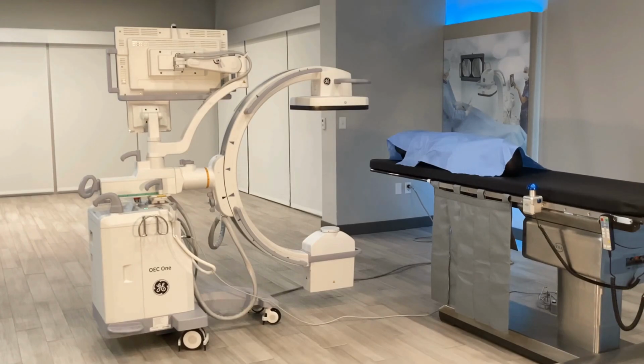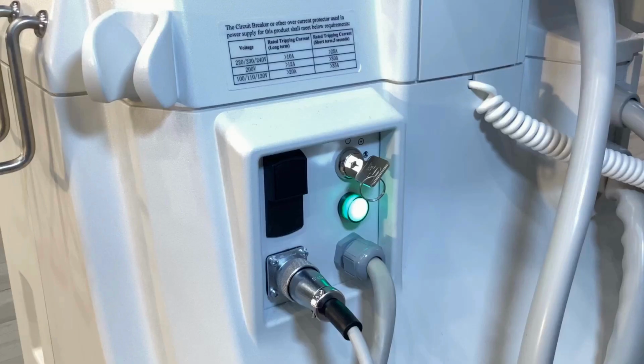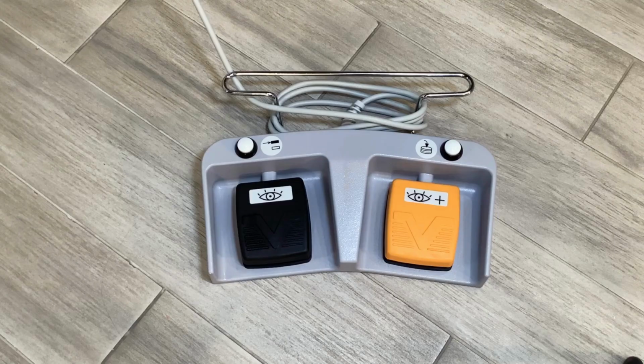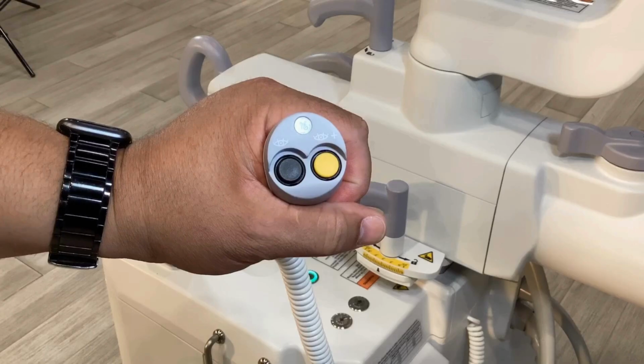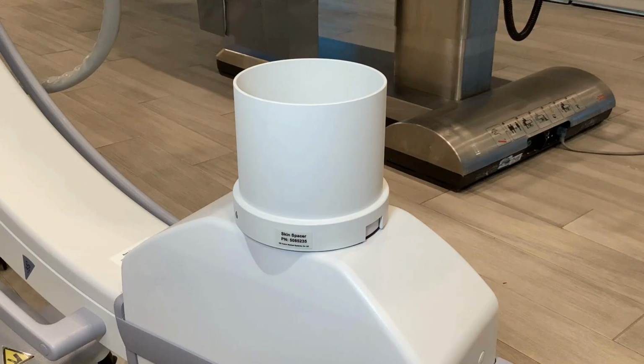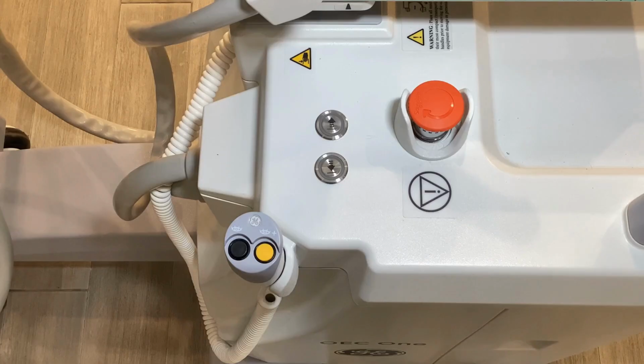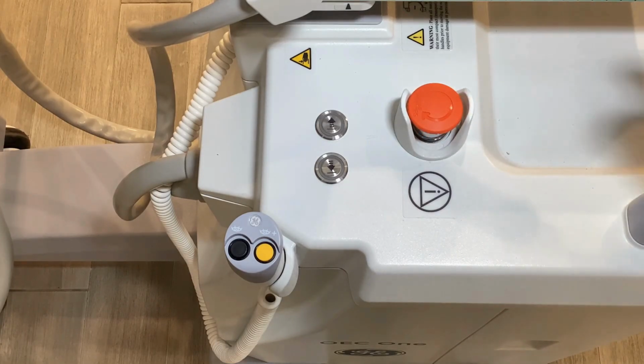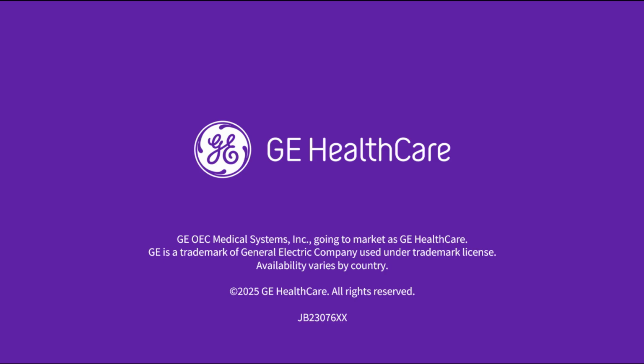The OEC One CFD has many additional features: incoming circuit breaker, foot switch socket, power indicator, and key switch, cord storage, foot switch, hand switch, skin spacer, emergency shutoff switch. To engage, press down. To release, twist clockwise. Please see the operator's manual for full description of all features. Thank you for watching.